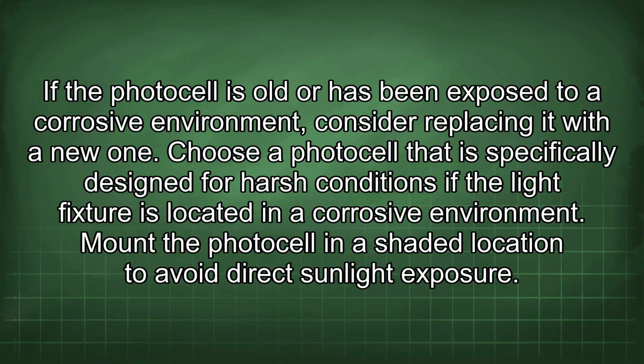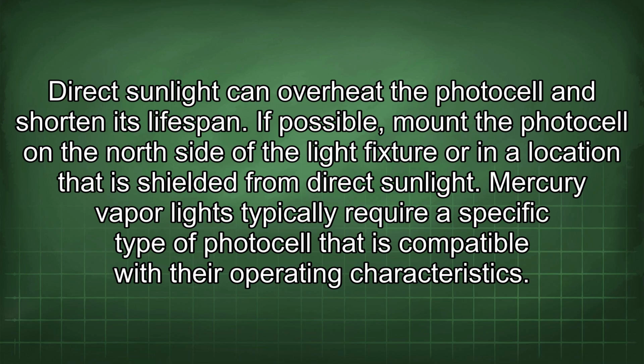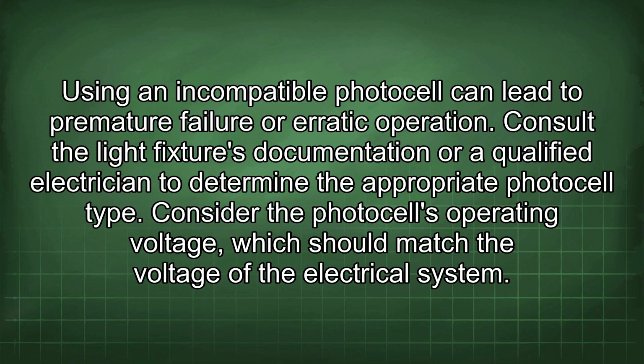Mount the photocell in a shaded location to avoid direct sunlight exposure. Direct sunlight can overheat the photocell and shorten its lifespan. If possible, mount the photocell on the north side of the light fixture or in a location that is shielded from direct sunlight. Mercury vapor lights typically require a specific type of photocell that is compatible with their operating characteristics. Using an incompatible photocell can lead to premature failure or erratic operation. Consult the light fixture's documentation or a qualified electrician to determine the appropriate photocell type.